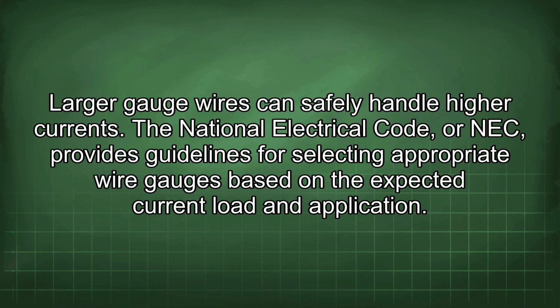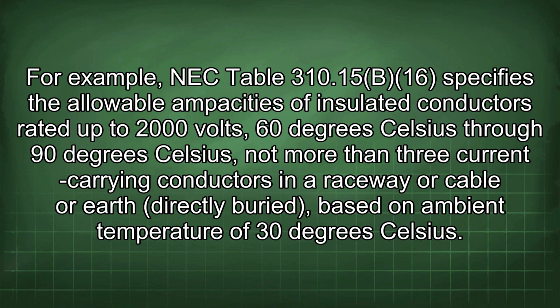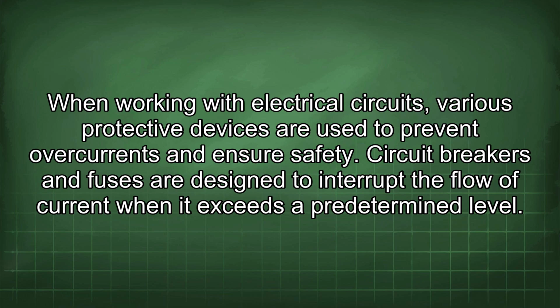The National Electrical Code, or NEC, provides guidelines for selecting appropriate wire gauges based on the expected current load and application. For example, NEC Table 310.15B16 specifies the allowable ampacities of insulated conductors rated up to 2000 volts, 60 degrees Celsius through 90 degrees Celsius, not more than 3 current-carrying conductors in a raceway or cable, or earth directly buried, based on ambient temperature of 30 degrees Celsius. When working with electrical circuits, various protective devices are used to prevent overcurrents and ensure safety.